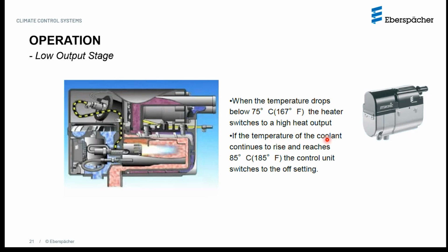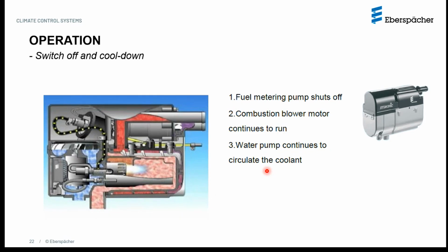Now, if the temperature of the coolant were to exceed 185 degrees, this is kind of the threshold, then the heater will be switched off automatically. At that point in time, the fuel pump will deactivate, the heater will go through a cool down cycle and switch off. This cool down cycle that I just mentioned is important for the safety of the heater and its parts. The fuel pump switches off, the fan continues to run, the coolant pump continues to run.